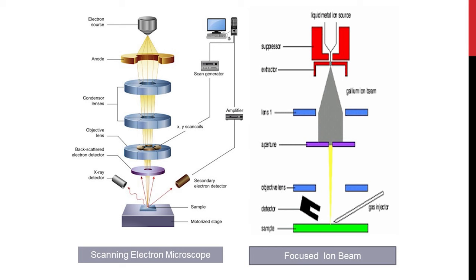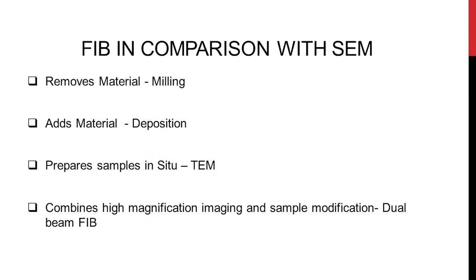This is a schematic of the ion beam and this is a schematic of the electron beam, which is the SEM and the FIB. What FIB can do in comparison with the SEM: we use electron microscopes for top surface morphology, but FIB can give you subsurface information as well. Since ions are heavier than electrons, they can remove material, which is termed as milling. FIB can also add material, called in-situ deposition or metal deposition. We can also prepare samples in-situ for TEM analysis with the help of the manipulator. Since it is a dual beam system with an SEM column, it can combine high magnification imaging with sample modification.